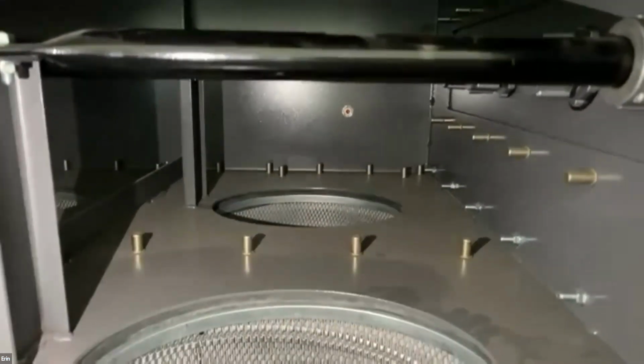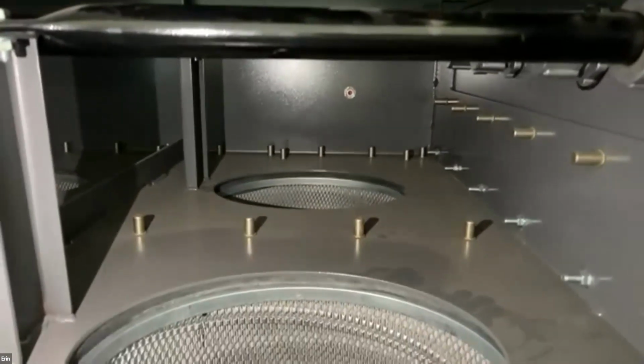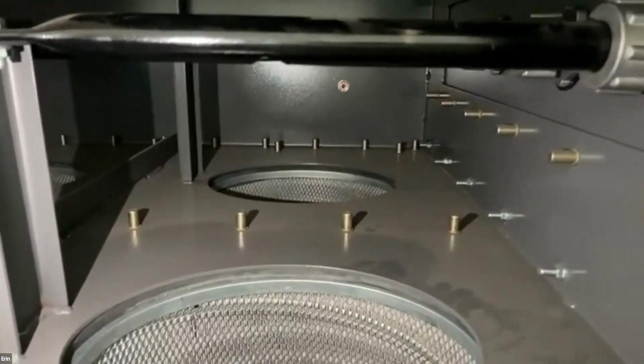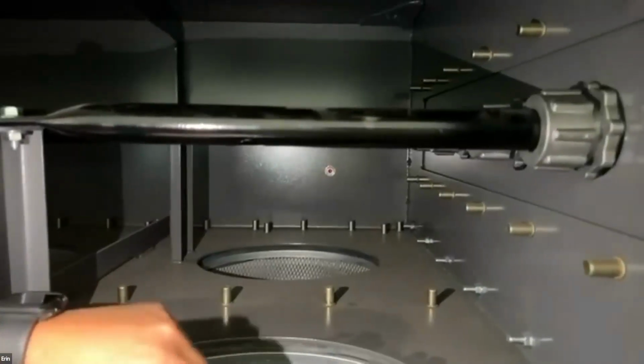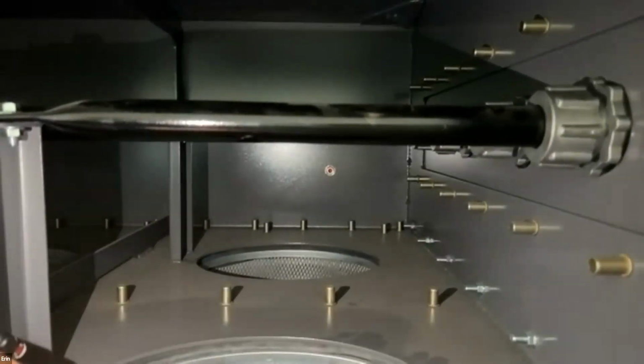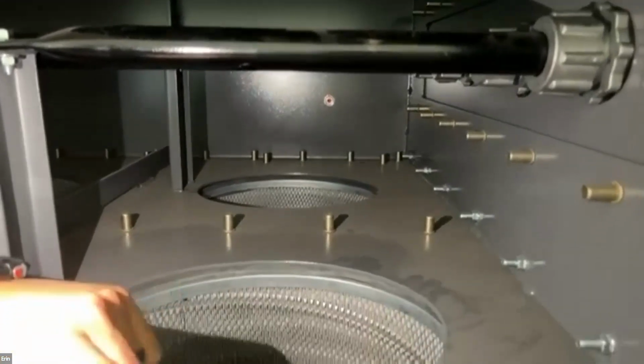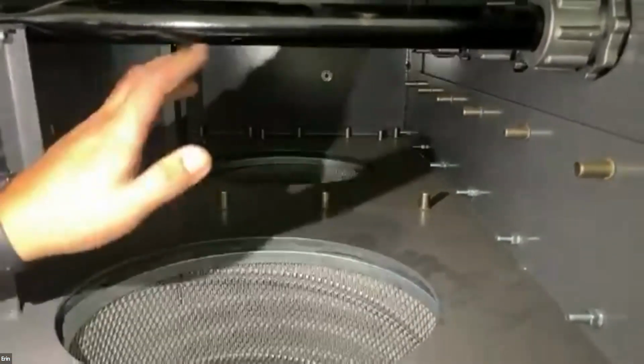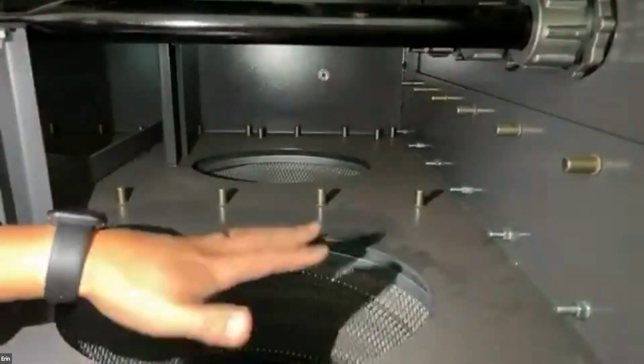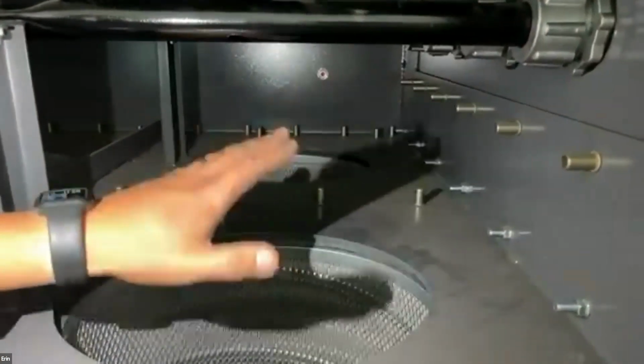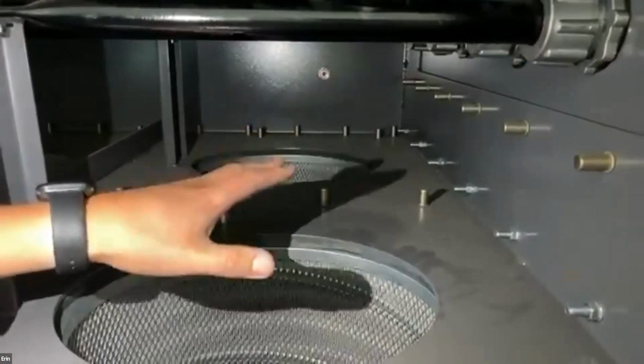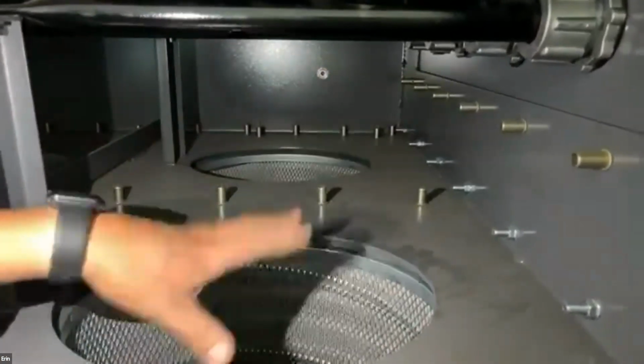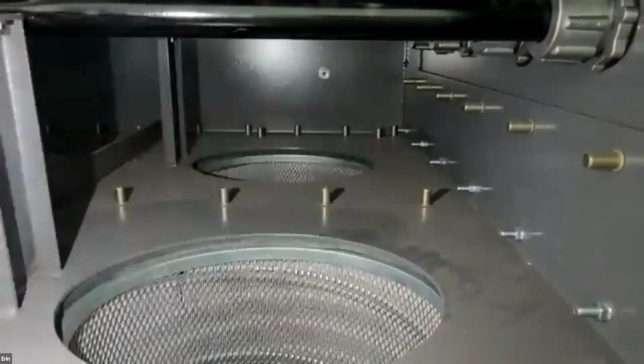But that distance and pressure from the inlet to the top of the filter will create a cone of pressure and push it all the way down to the bottom of the filter, pushing all that air back out, shaking it, shocking it, kind of knocking it out. Yeah, exactly. It's very much like your shop vac at home where you take the filter out and bang it against the wall. This one just has an internal self-cleaning mechanism that pushes air down through there. And much like the shock wave we talked about when an explosion happens, the shock wave of the air goes down through and pulses the filter clean.